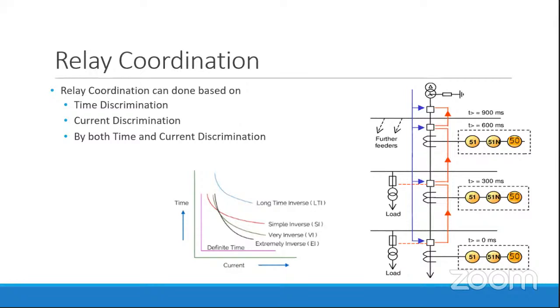Okay, let's go deeper into relay coordination. Relay coordination can be done based on two criteria or two discriminations. We can say the first one is time discrimination and the other is current discrimination. A combination of both, time and current discrimination, is generally used for reliability purposes.